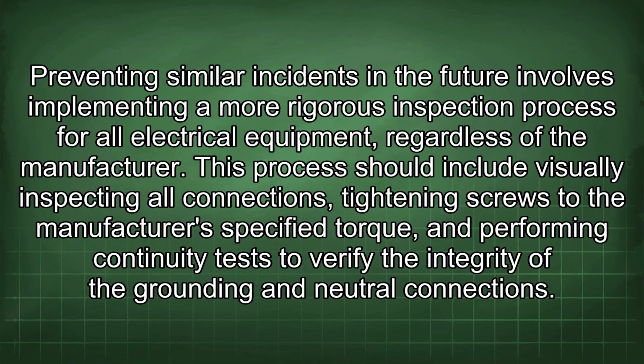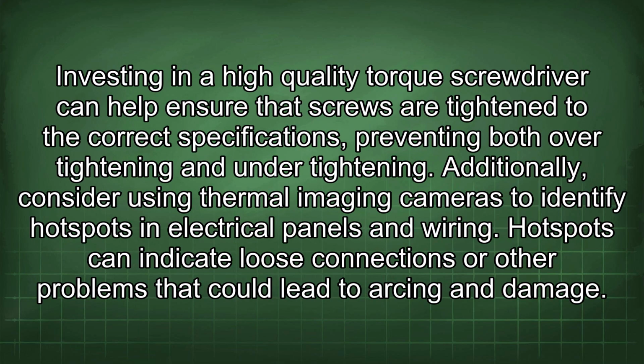Preventing similar incidents in the future involves implementing a more rigorous inspection process for all electrical equipment, regardless of the manufacturer. This process should include visually inspecting all connections, tightening screws to the manufacturer's specified torque, and performing continuity tests to verify the integrity of the grounding and neutral connections. Investing in a high-quality torque screwdriver can help ensure that screws are tightened to the correct specifications, preventing both over-tightening and under-tightening. Additionally, consider using thermal imaging cameras to identify hotspots in electrical panels and wiring. Hotspots can indicate loose connections or other problems that could lead to arcing and damage.